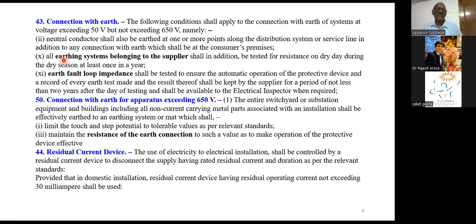It can be easily handled by the MCBs and your residual current device if you are not comfortable with your MCB as well as your TT system. So what the standards, regulation 44, says is that use of electricity in an electrical installation shall be controlled by the RCD. So here you cannot be expected to have the required loop impedance in a TT system where the residual current device is essential.